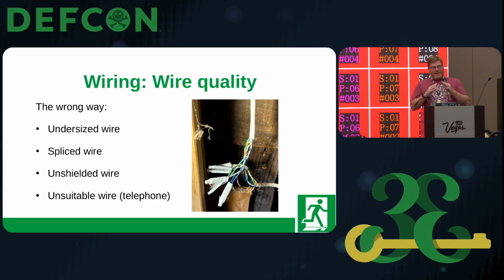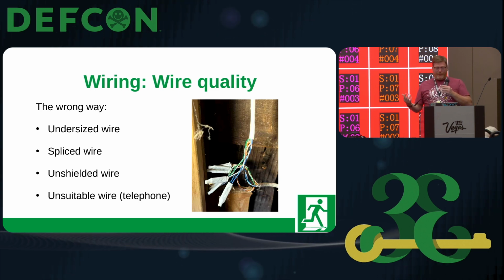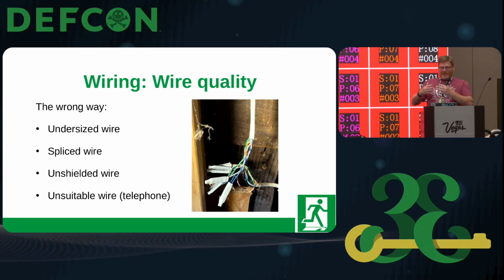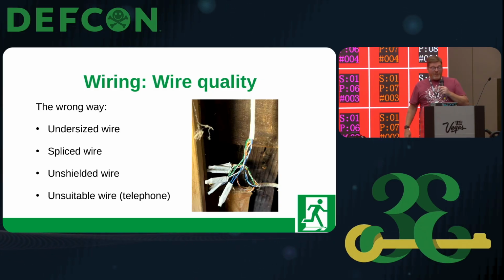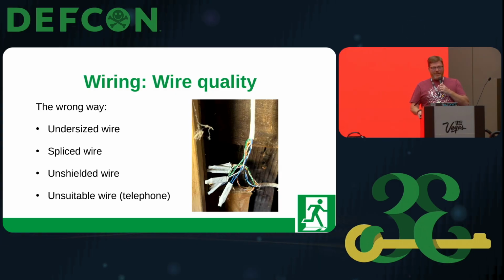Typically what I see is a lot of kind of whatever was on the truck or whatever we got at a discount from the place that we buy our wire is going to be what we're going to use. So, the power to our door lock, well, it's a little far for this 18 gauge wire, but we're going to go ahead and run it anyway because that's what we've got. I've seen spliced wire where they ran out of wire or something and they spliced it together, or maybe it got cut or something. A lot of unshielded wire, again, for card readers, this is particularly an issue where the card reader can crash and you actually have to unplug it from the panel to get it to start working again. And then just plain unsuitable wire, like I've seen Ethernet wire used for wiring this stuff.